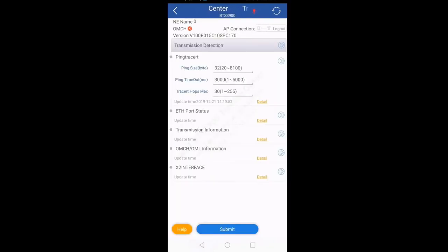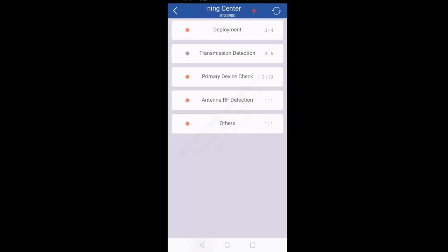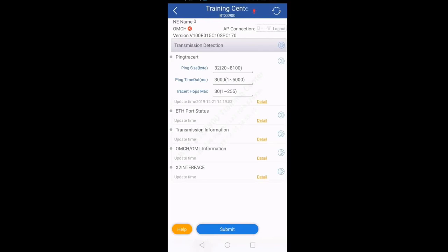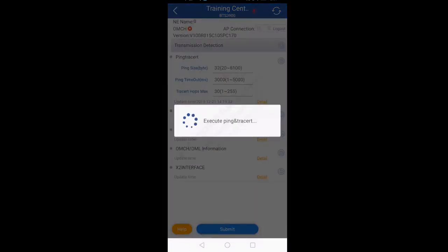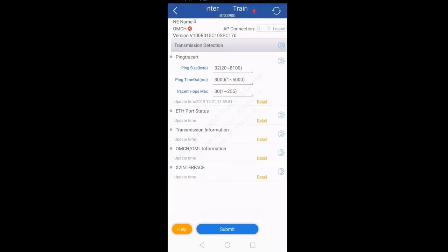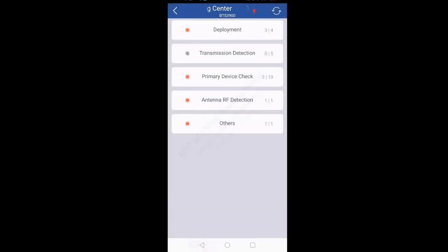If you want to check transmission, go to the second option: Transmission Detection. The first option is Ping Tracer — click the play button and it will give you the ping test. Here we don't have any transmission connected so it will not give any value, but on site it will give you the ping result. So in this way, using WDT tool, you can upload the configuration, check active alarms, check VSWR values, check board status, check the GPS clock link, and do the ping test — all with one app, without the need of a laptop.